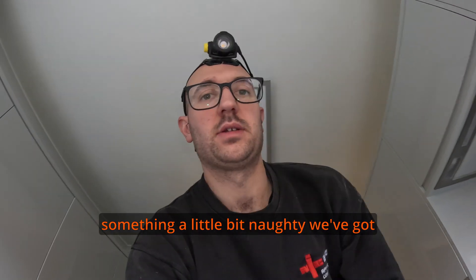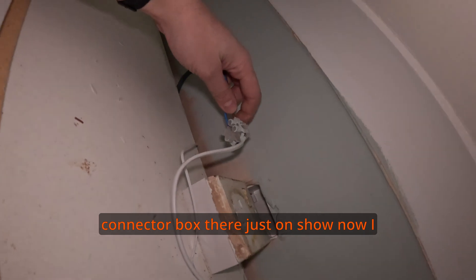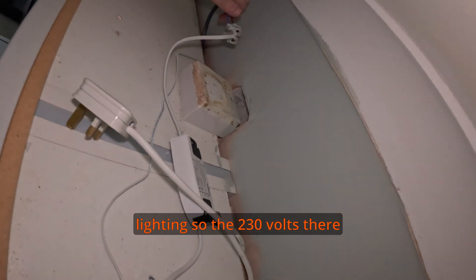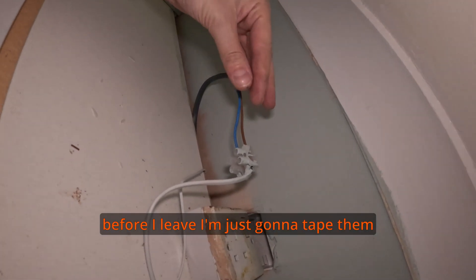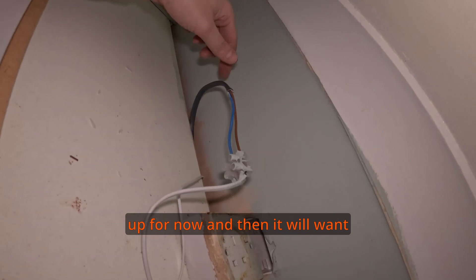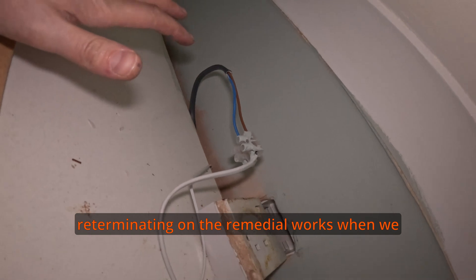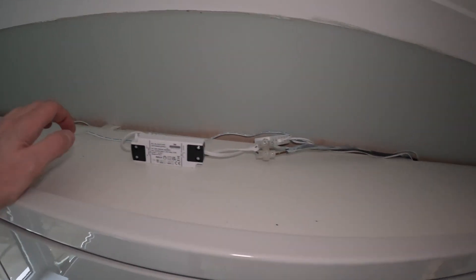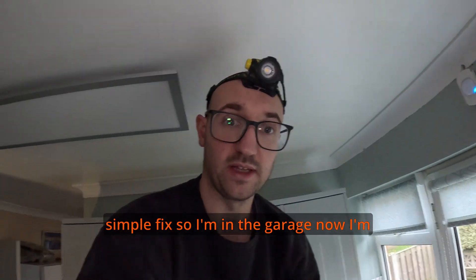Just while I'm looking at this extract, something a little bit naughty — we've got a connector box there, just on show. I know that's for the under-counter lighting, so there'll be 230 volts there. Before I leave I'm just going to tape those up for now, and then it'll want re-terminating on the remedial works. A little bit naughty, but a fairly simple fix.